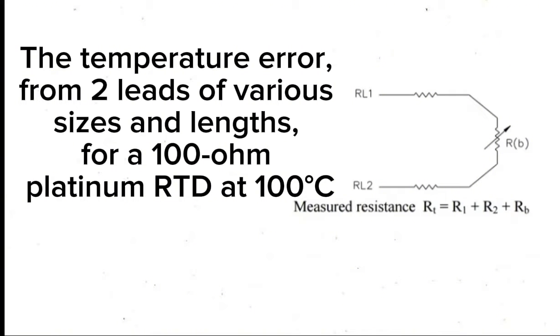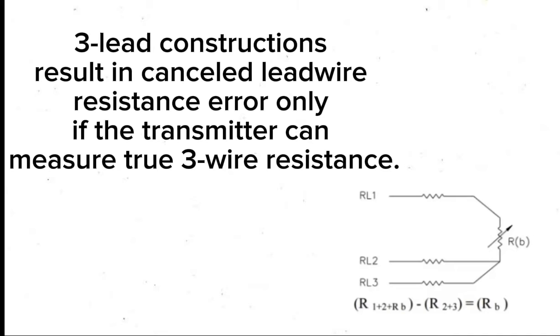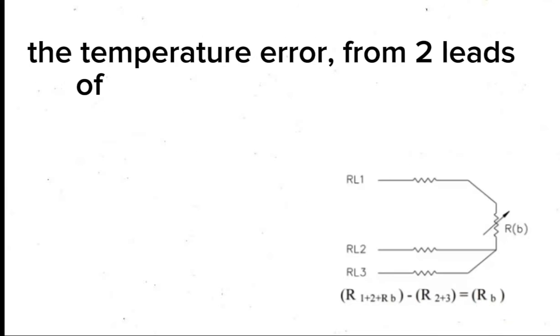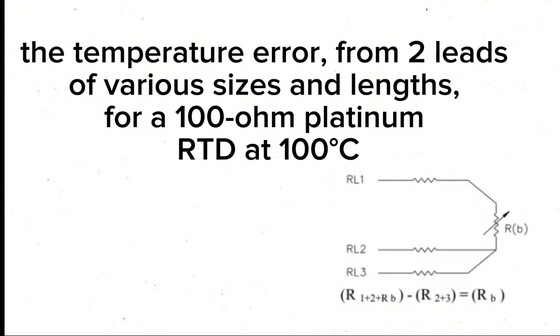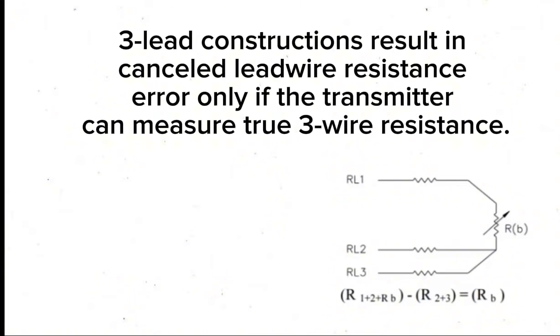Three-lead constructions result in cancelled lead wire resistance error, but only if the transmitter can measure true three-wire resistance. The temperature error from two leads of various sizes and lengths for a 100-ohm platinum RTD at 100°C is eliminated under this condition.